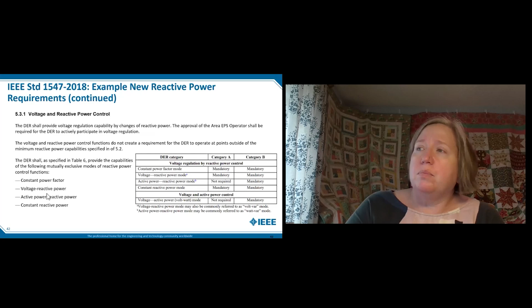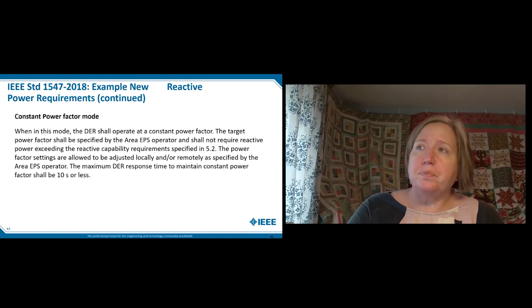So getting into what these reactive power modes are: under constant power factor mode, the DER operates at a constant power factor. It's going to be specified by the area EPS operator, and shall not require reactive power exceeding the reactive capability. The power factor settings can be adjusted locally or remotely as specified. And the DER has to maintain the constant power factor in under 10 seconds. So volt-var, you can see this is a piecewise linear curve, where you have the injecting, you have the absorbing, you have the deadband, and this is all settable.